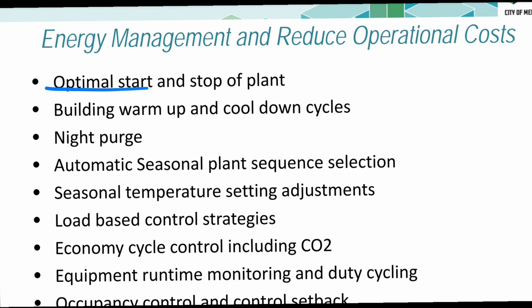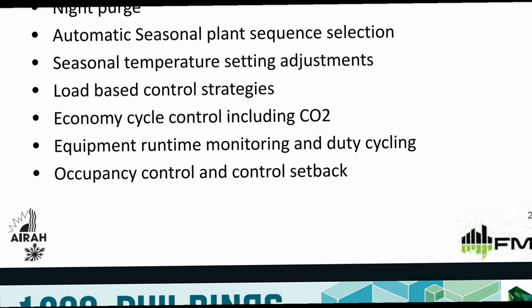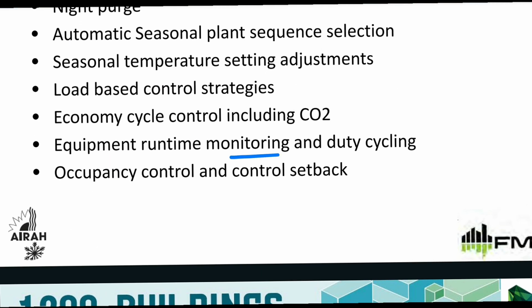optimum start and stop of plant, building warm-up and cool-down cycle, night purge, automatic seasonal plant sequence selection, seasonal temperature setting adjustment, load-based control strategy and economy cycle control including CO2. Okay, equipment runtime monitoring and duty cycling, occupancy control and control setback.